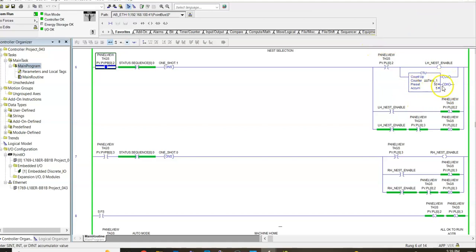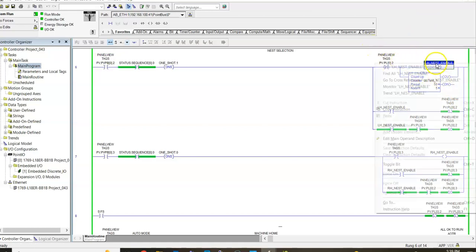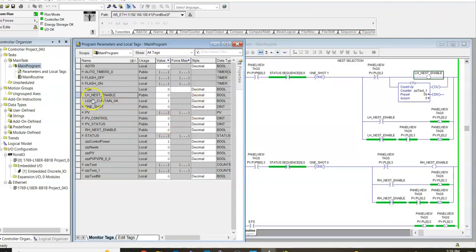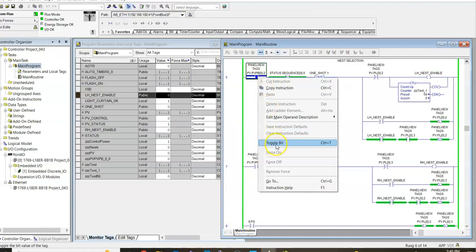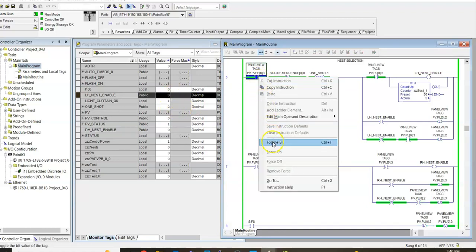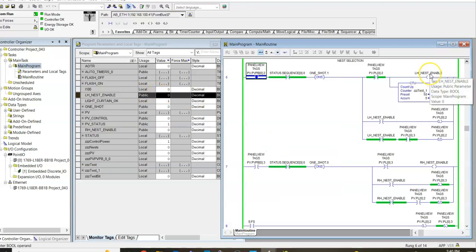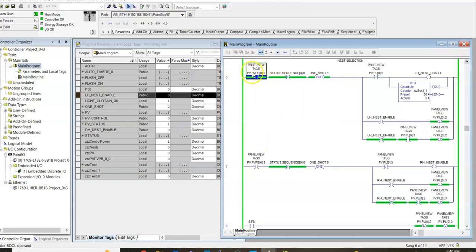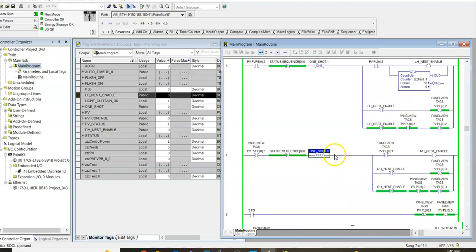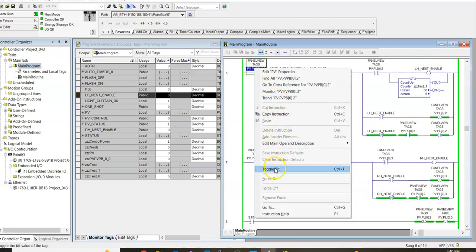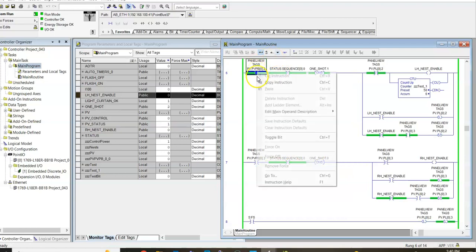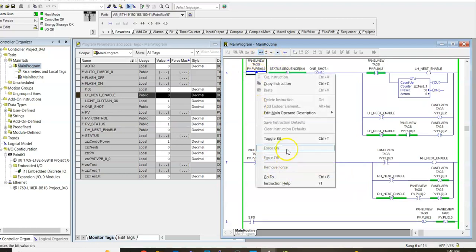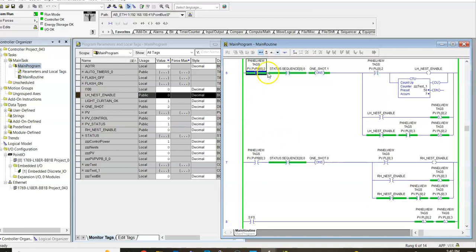How do we know? Because I don't see this left-hand nest being enabled. So I put a counter down here just for the testing. Let's go ahead and monitor that. Watch this. On our left-hand nest enable, as I toggle this bit on and off, I'm not seeing that left-hand nest enable right here go high at all. That's why I put this counter on there. Because if I didn't, you wouldn't see it. You wouldn't see that bit on. So we know that we have both nests available to us because on our first scan, or as we toggle this bit on and off, we're choosing which nest we want to use in our production.